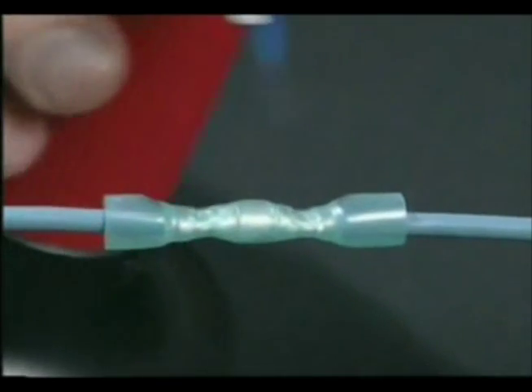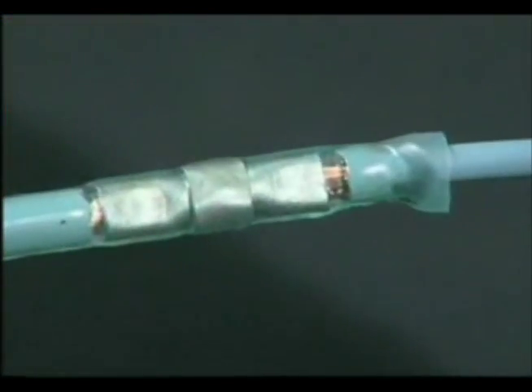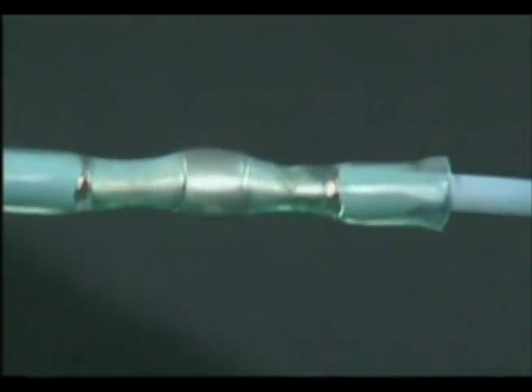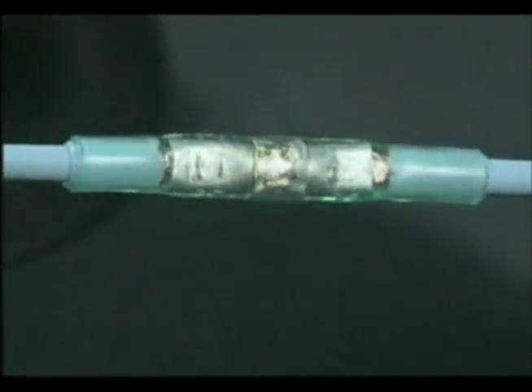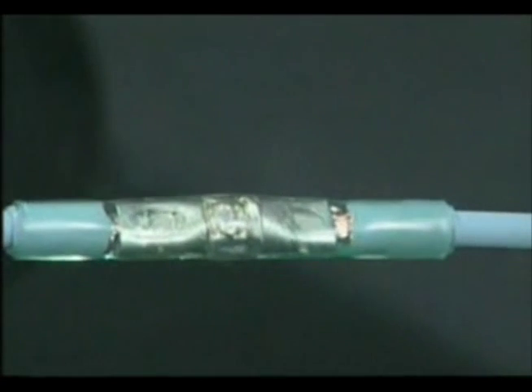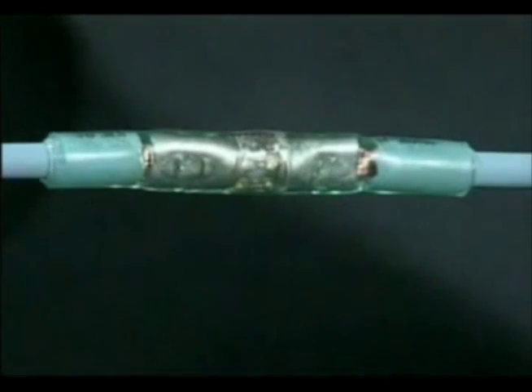Heat the connector evenly from the center out to the ends until the tubing is fully recovered. Continue to distribute the heat over the solder sleeve. Do not isolate the heat too long in one place. After the solder flows into the center opening in the barrel, remove the connector from the heat and let it cool.